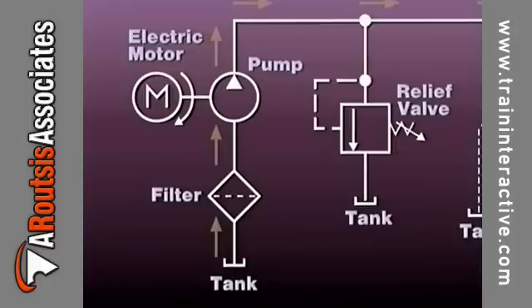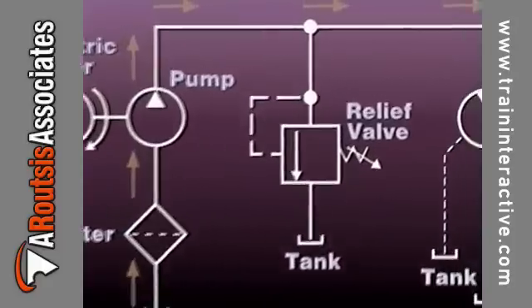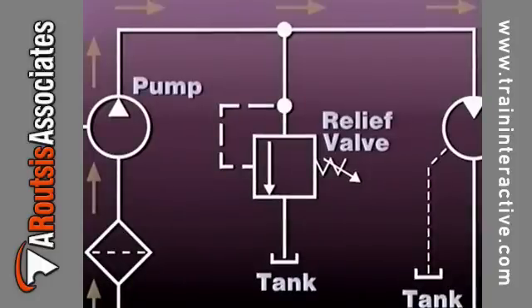The amount of resistance is controlled by the relief valve setting. When the system pressure reaches the spring setting of the relief valve, any additional fluid is returned to the tank.